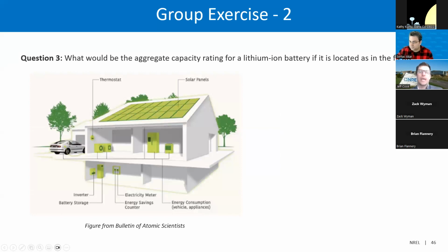All right, so this is aggregate capacity rating for lithium-ion batteries. So you can have 20 kWh for an individual battery, but we're talking aggregate capacity. So how many batteries could one install in the basement? In this case, now there can be modifications to this, but per the model code, it's 40 kWh. So you could have 2 batteries if they were both rated at 20 kWh, or some combination of that, depending also on what your local amendments are for that.